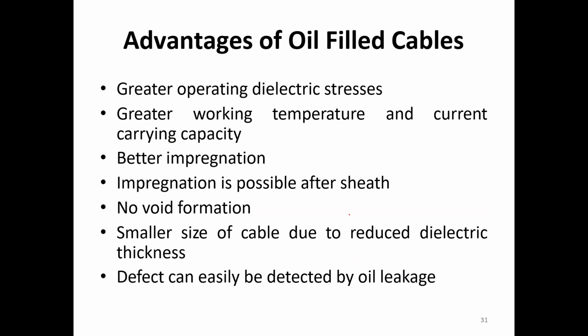What are the advantages of oil filled cable? Greater operating dielectric strength, greater working temperature and current capacity, better impregnation is possible after sheath, no void formation, and smaller size due to reduced dielectric thickness.